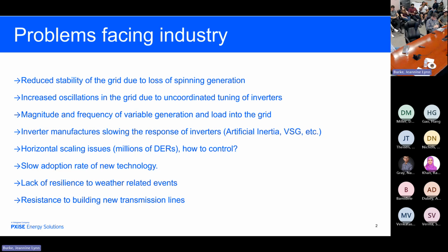We also are facing some problems with industry. The industry is trying to solve this problem, in my opinion, by adding artificial inertia to their existing grid-following inverters. That is, from my perspective, from a control engineering perspective, the wrong approach. We need to have inverters that are, first of all, voltage source inverters, and second of all, they need to respond very fast to commands.